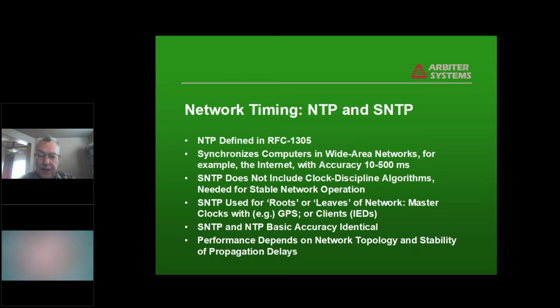The basic accuracy is the same because the basic synchronization method, the way of transmitting and receiving, is the same. The difference with NTP is that it is intended for use in intermediate level servers that are interacting with a bunch of different time sources in different places with different delays, and servers coming and going, that sort of thing. Performance of NTP and SNTP in a substation depends on network topology and stability of propagation delays. In wide area networks the propagation delays are unstable, like I mentioned, but in a substation the propagation delays can be very consistent.